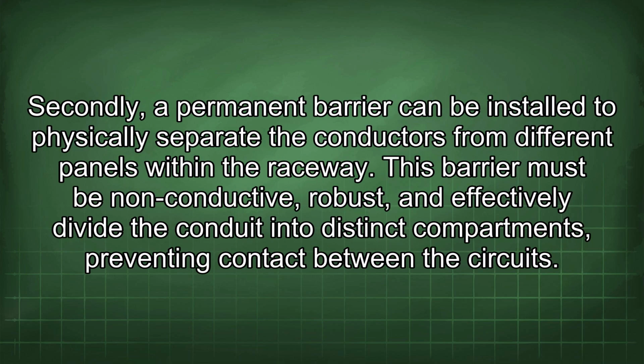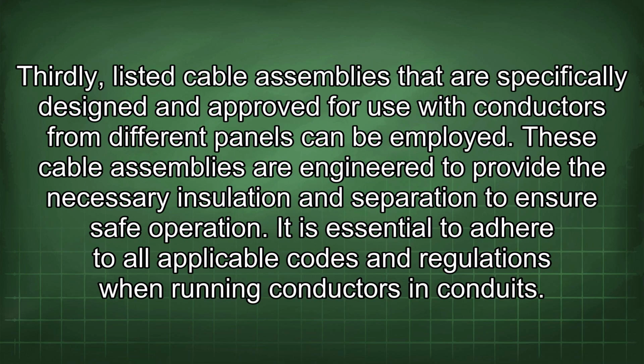Secondly, a permanent barrier can be installed to physically separate the conductors from different panels within the raceway. This barrier must be non-conductive, robust, and effectively divide the conduit into distinct compartments, preventing contact between the circuits. Thirdly, listed cable assemblies that are specifically designed and approved for use with conductors from different panels can be employed. These cable assemblies are engineered to provide the necessary insulation and separation to ensure safe operation.